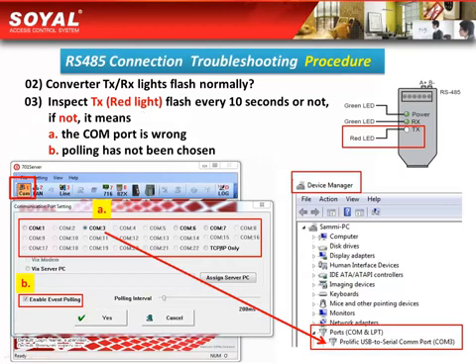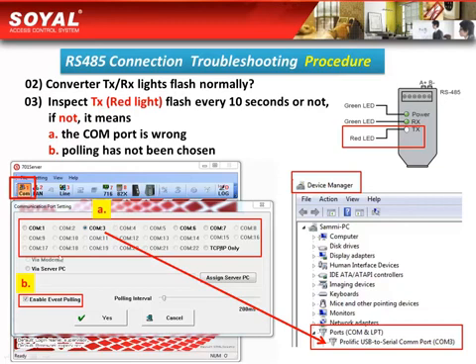If the TX or Rx light is not flashing normally, there are two possible reasons. First, the COM port may be wrong — use the Device Manager to confirm your COM port. The second possible reason is that polling has not been enabled. Here you can see the 'Enable Event Polling' option. Remember, event polling must be selected.